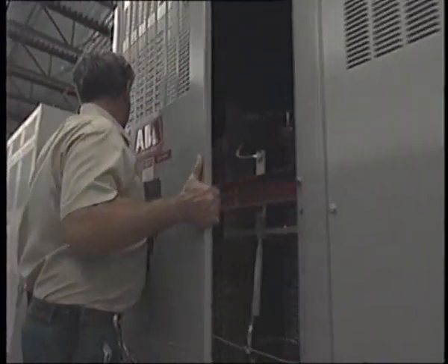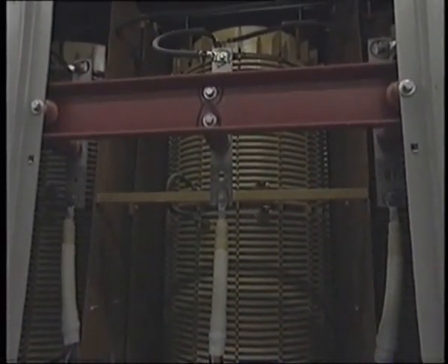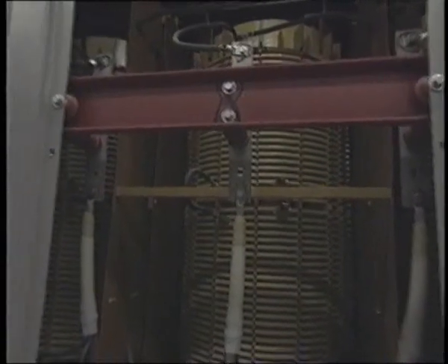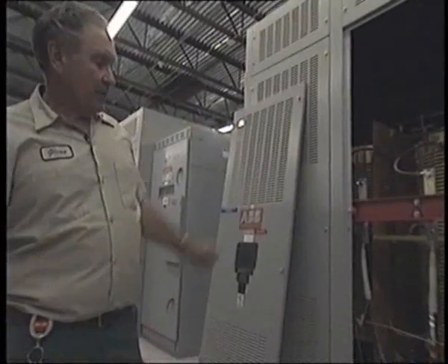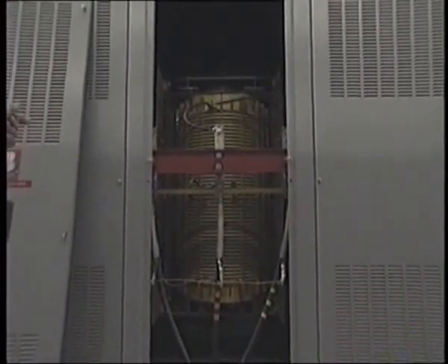The Luxor hotel needs its own bank of transformers to step the high voltage alternating current down to various voltages. You're seeing three big coils in there — that reduces the twelve thousand four hundred volts down to four thousand one hundred and sixty volts. This is the power used for air conditioning units. Then it goes to another bank of transformers that breaks it down to 120/208 volts, which is used for lighting, slot machines, gaming, and whatever else it might be.